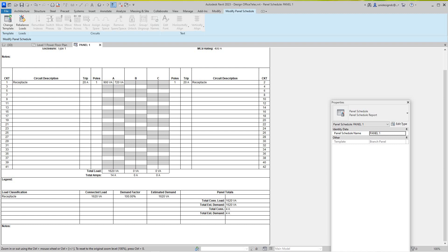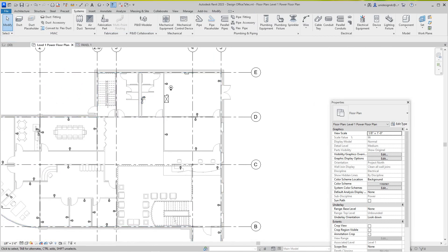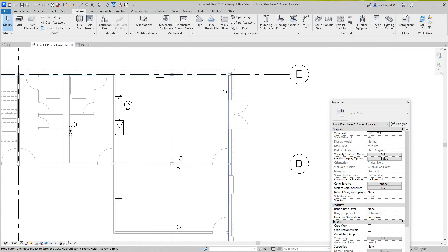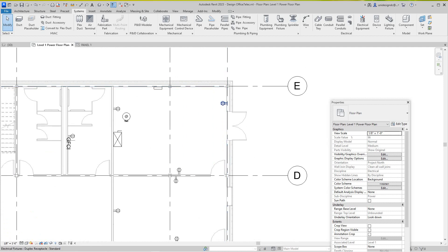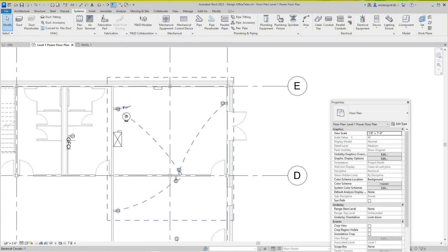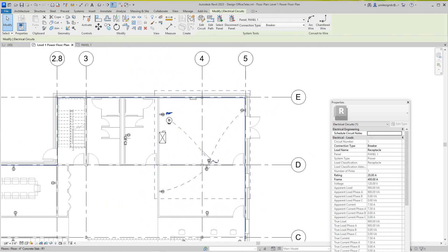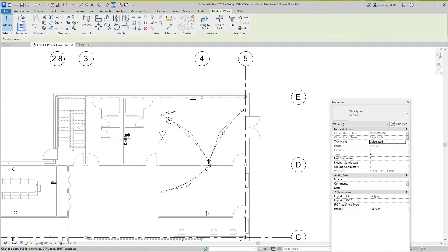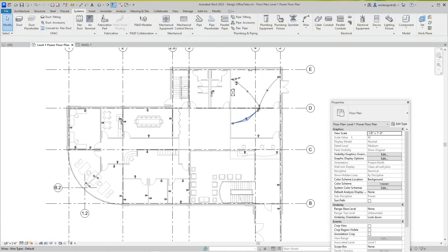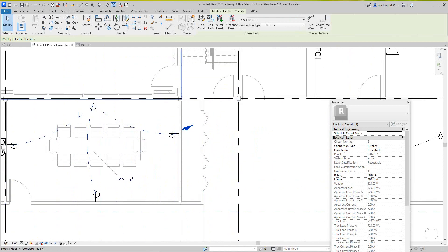Now we're going to go back to our plan view and I want to show you how this circuit really works. I'm going to select this one here, then Tab to select it — and there's my circuit and there's the home run. You can select the wire here. I'm going to add our wire — that's pretty much standard — and then Finish. There's one circuit. Let's do this one here. Tab it and there's our home run going back to our panel.